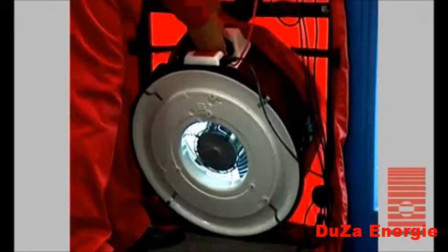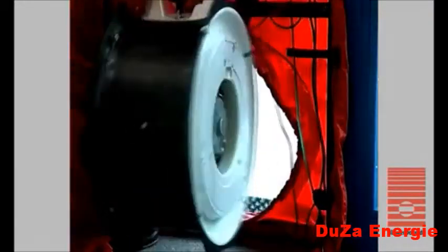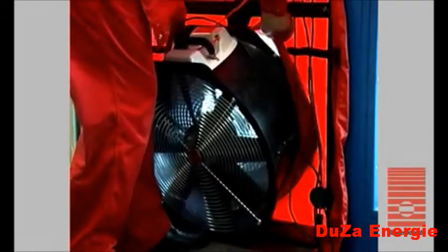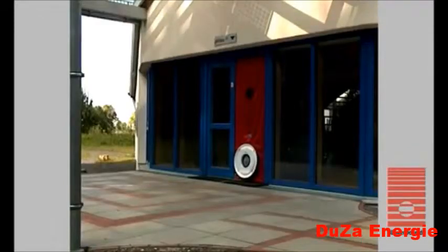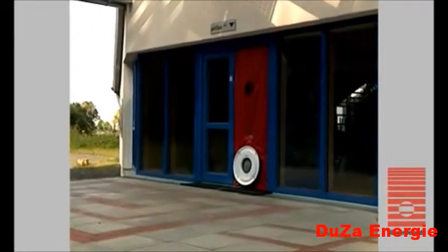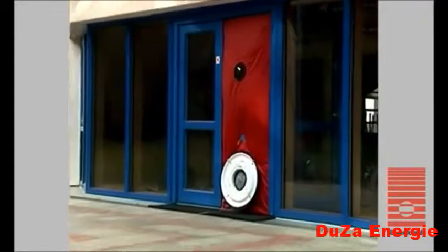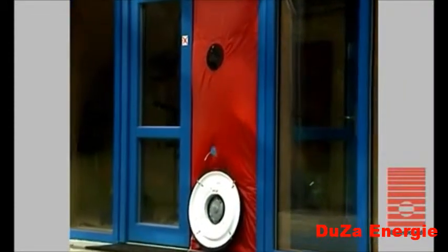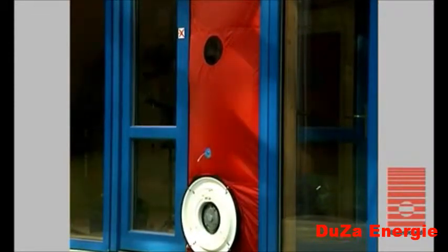In addition to the depressurization test, the blower door can be used to perform a pressurization test on the building. For this technique, the fan is installed in the frame with the flow rings turned to the outside and the blue tubing is connected to the upper pressure tap on the nylon panel. During a pressurization test, air is blown into the building, which forces air to leak from the inside of the building to the outside.